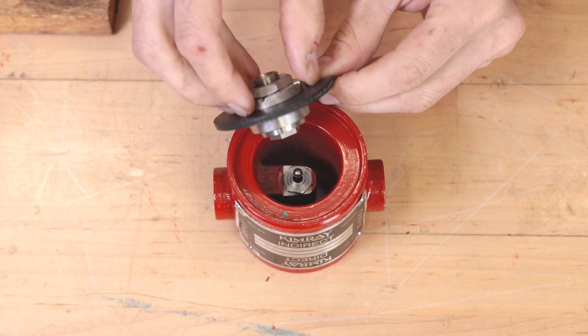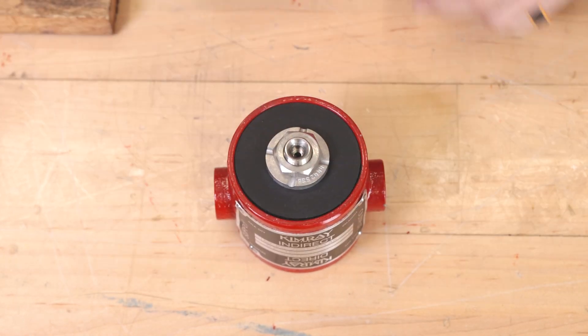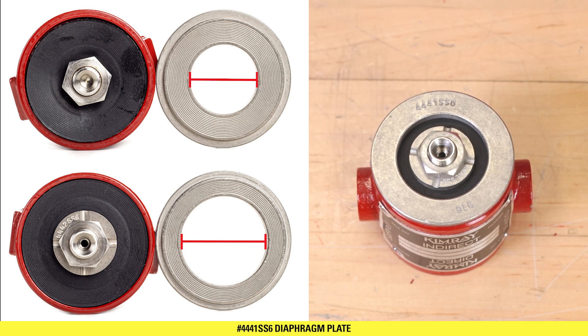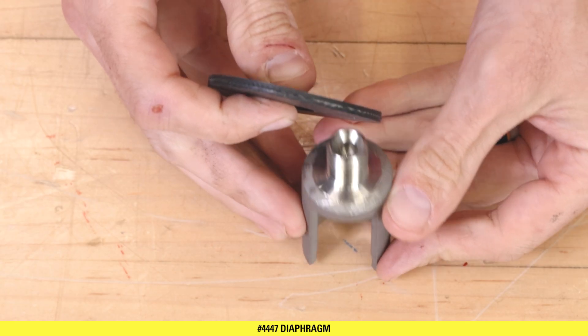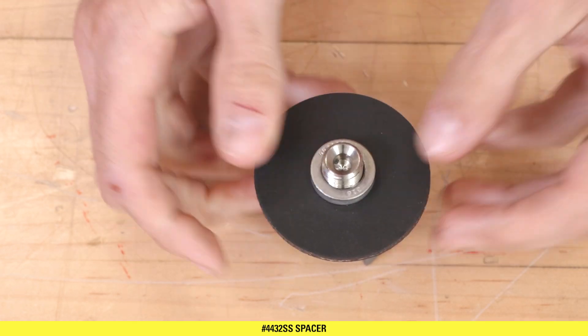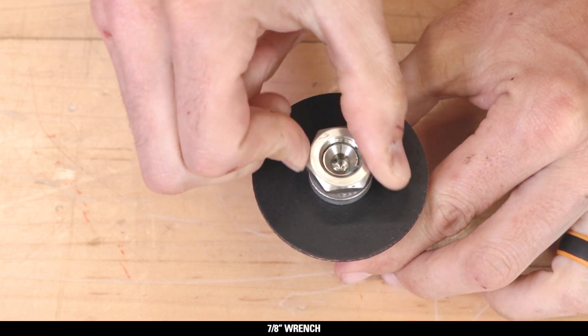Install the 44-47 diaphragm. Place the upper seat assembly over the small ball of the pilot plug. Then place the 44-41 SS6 diaphragm plate on top of the diaphragm. Install the 44-47 diaphragm over the stem, followed by the 44-32 SS spacer ring. Screw on the diaphragm nut with a 7/8 inch wrench.